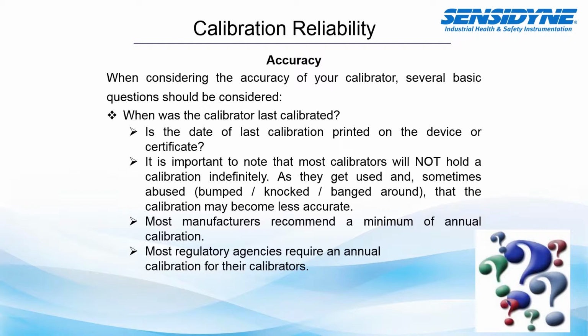Now, when you send them back, some companies just require calibration and a return of device. However, to get the most out of your calibration, you may want to request as-found data also be reported back. Now, some manufacturers or calibration labs will charge additional for this service. However, it's a valuable piece of information to understand how much drift occurred since the last time your device was calibrated.